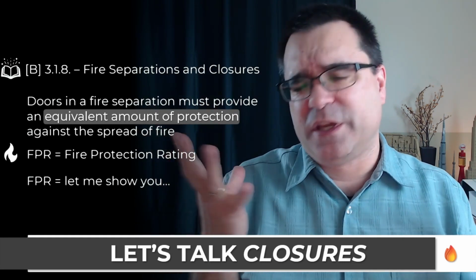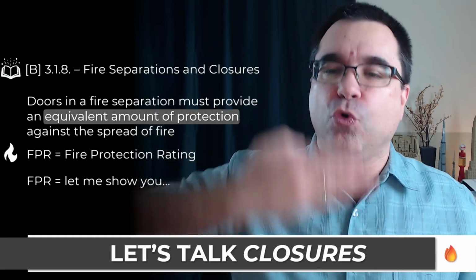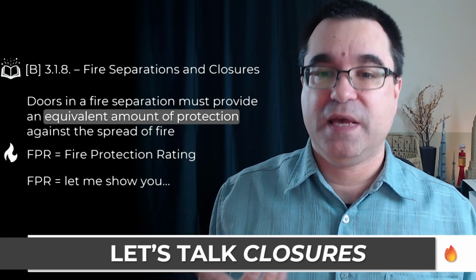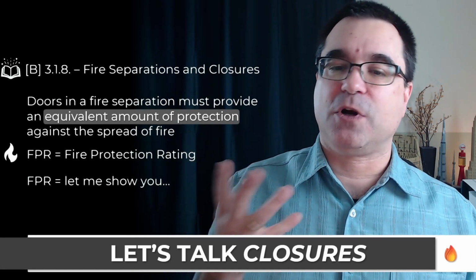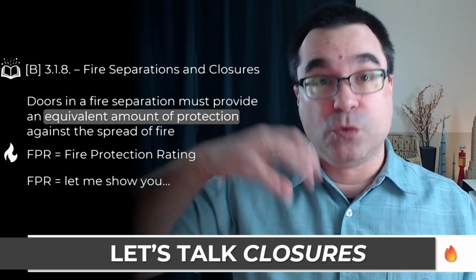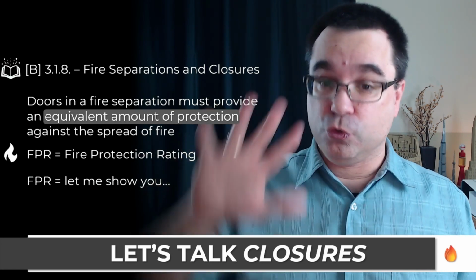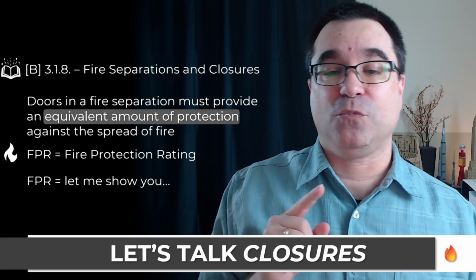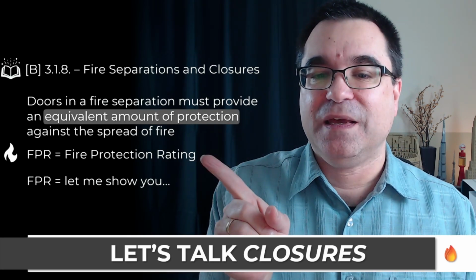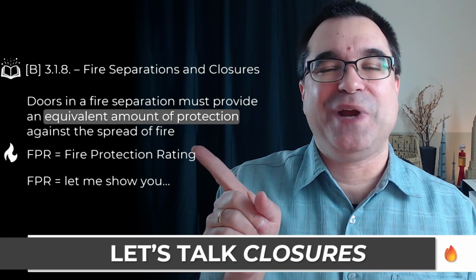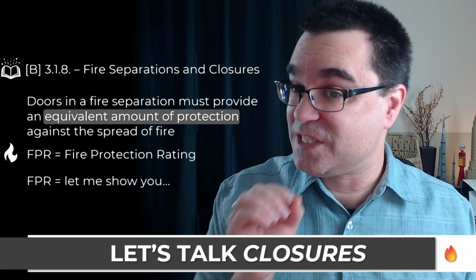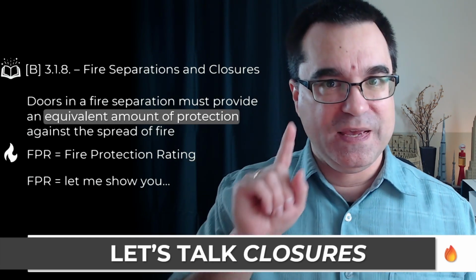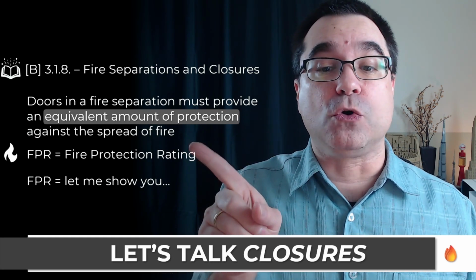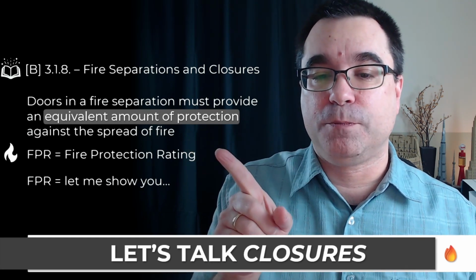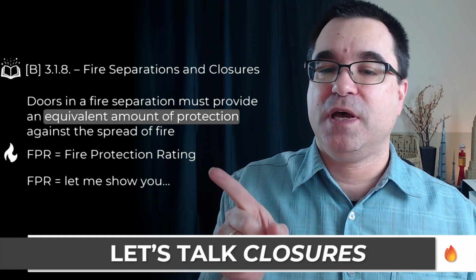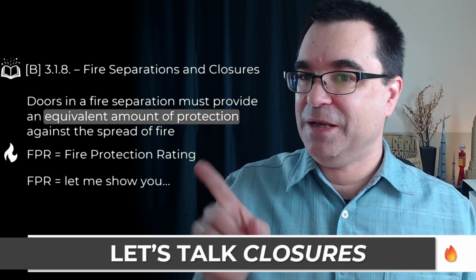So let me use regular English words, okay? Whatever door you put in a fire separation has to provide a similar amount of protection than would be there if there wasn't a door, if it was just a solid wall, okay? Now here's an interesting thing. Doors are not rated according to a fire resistance rating. Remember FRR? Instead, doors are rated according to a fire protection rating, FPR.